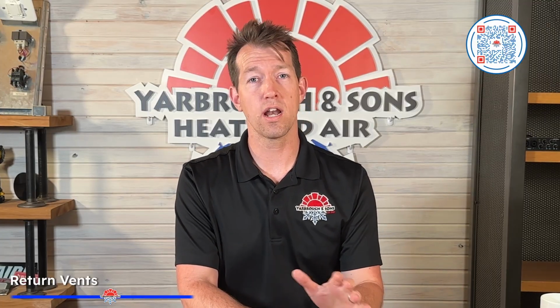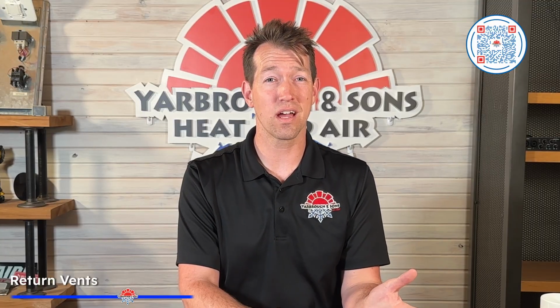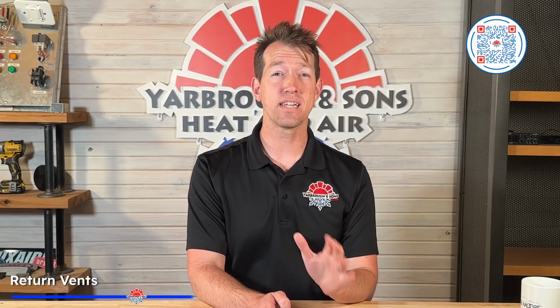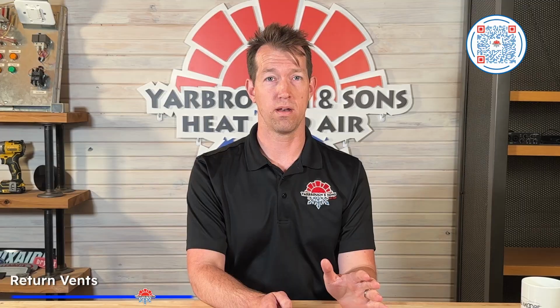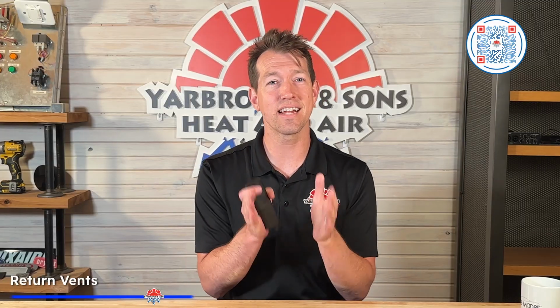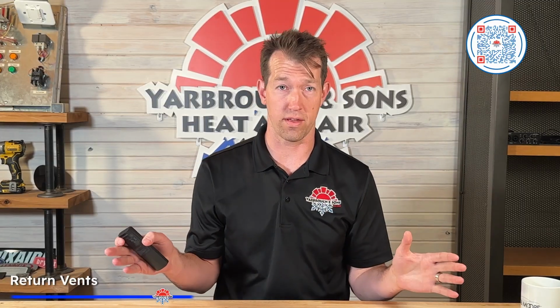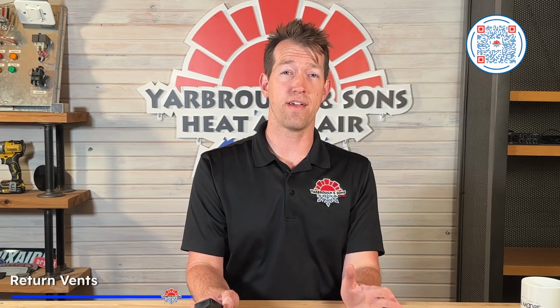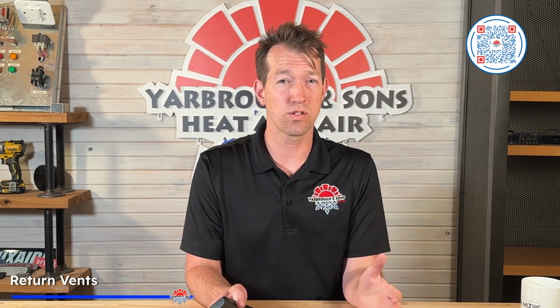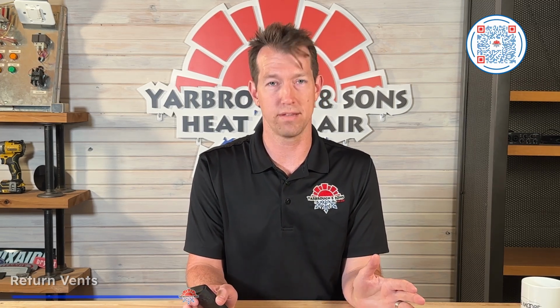Again, restricted airflow means reduced cooling capacity and a higher risk of a frozen coil. Check every single return vent in the house before you call anyone. Make sure there's at least 6 inches of clearance all around them. Guys, this is a $0 fix. And honestly, it accounts for more service calls than you would like to believe. Frozen evaporator coils. It's $0 if you can catch it early.